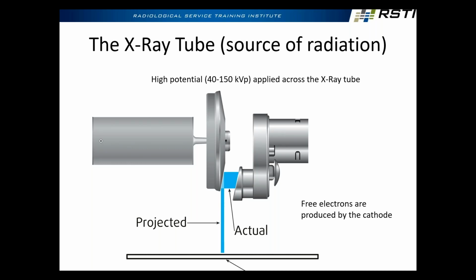Now, the tricky bit here is that we have a diverging beam that we always see drawn that way coming out of the X-ray tube. And it's not because we're doing a bank shot off of the face of the anode, all right? Why do we call X-ray radiation X-ray radiation? Because it radiates. Yeah, it radiates in all directions, right? So we have X-rays being produced at an infinite number of points within this focal spot, and they are going in every direction.